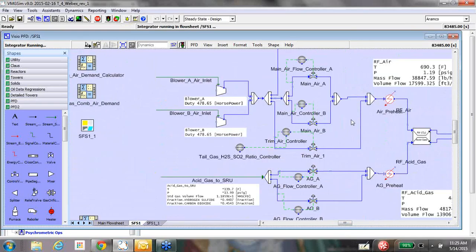All this information is really handy and helpful when there is any emergency shutdown or any equipment failure, for example, any valve shot, or they want to replace it. So they can configure that equipment here, put in the new valves' CV codes and other data, and see how it behaves in case it is not identical to what they are replacing.